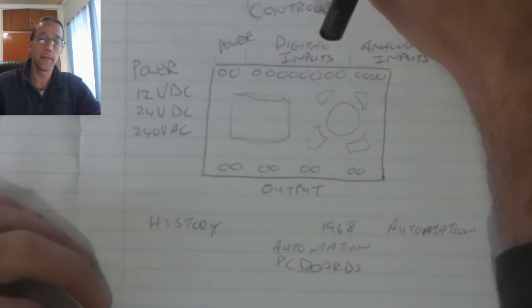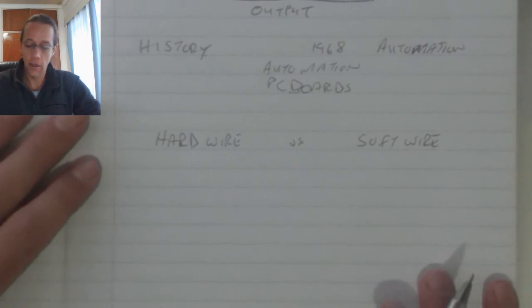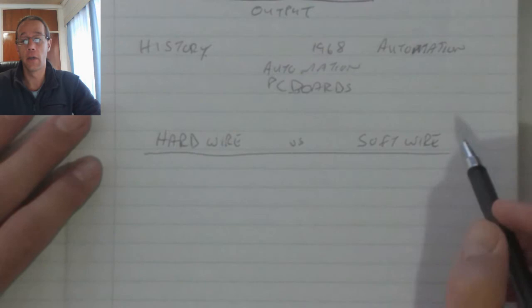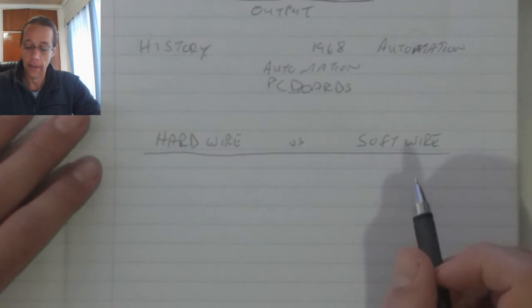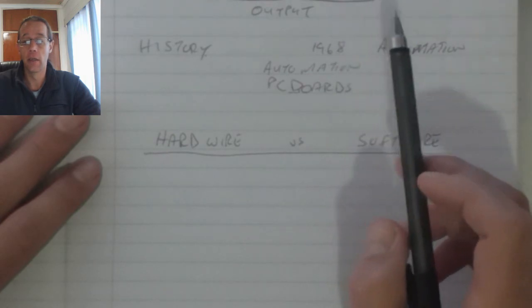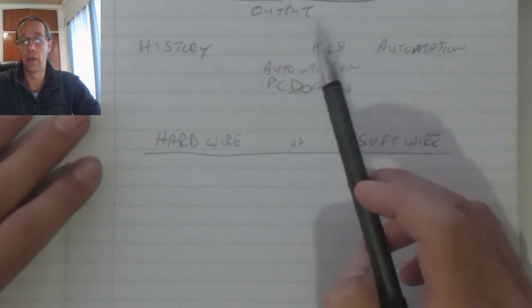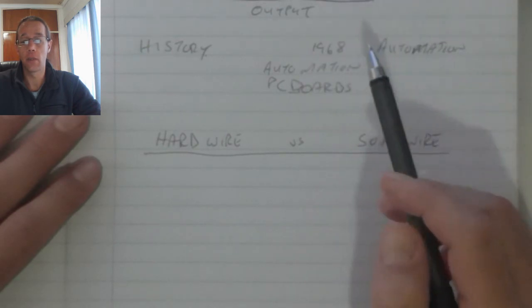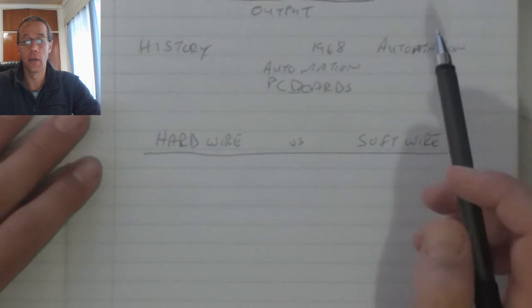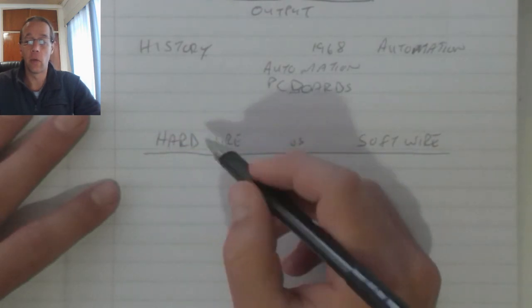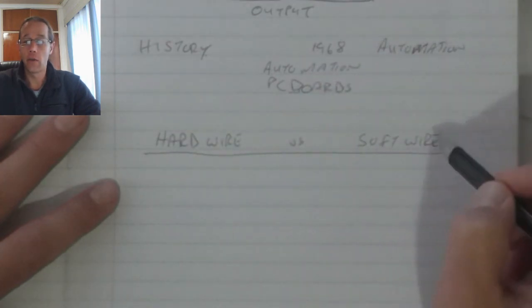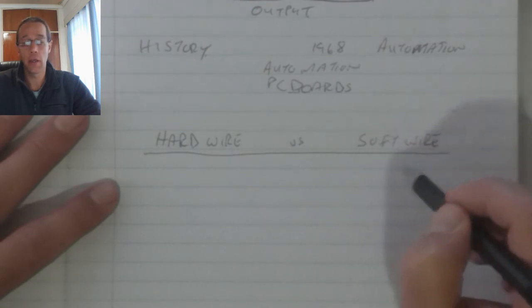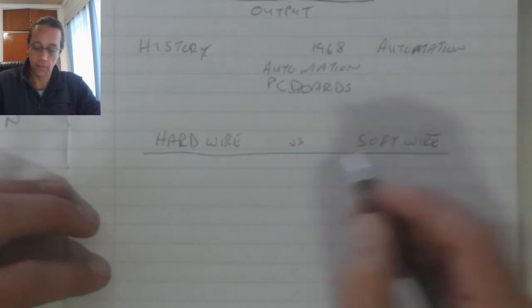Hard wiring versus soft wiring. When it comes to hardwired and softwired devices, because the PLC is an electric device we are going to need electrical connections, in other words wires that run from the PLC to the devices that's being controlled. Now because of the voltage and current limitations of the PLC, PLCs typically cannot connect directly to a motor. As a result we connect them to contactors or we can even connect them to relays which then connects them to contactors. This is a safety aspect. Hardwiring refers to one contactor connecting to another, whereas softwiring all those connections are replaced by a computer program that is uploaded into the PLC.